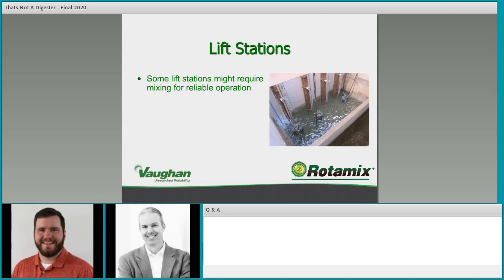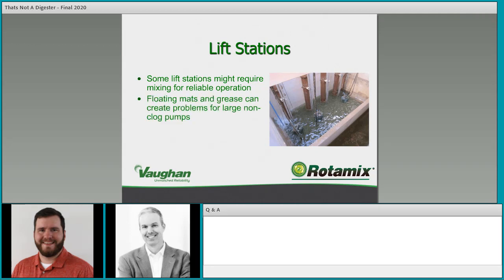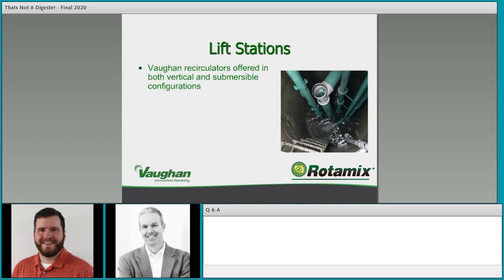These factors can change lift station design, and mixing can help alleviate a lot of the common problems. Floating mats and grease can create problems for large non-clog pumps. Rapid mixing and turnover are required because flow is coming in and moving out fairly quickly — the hydraulic retention time in a lift station is generally not very long. You need rapid mixing and turnover to keep up with loading and manage it.